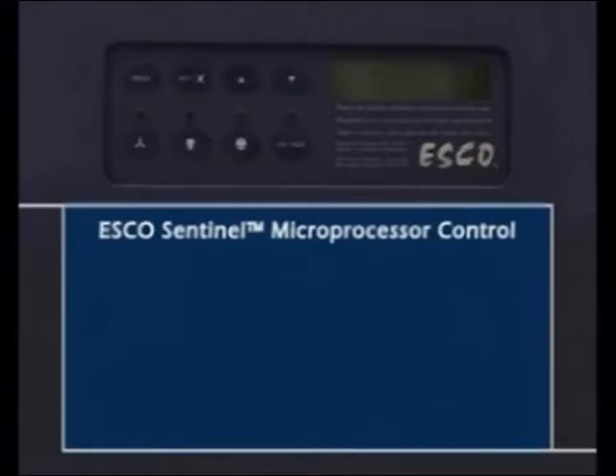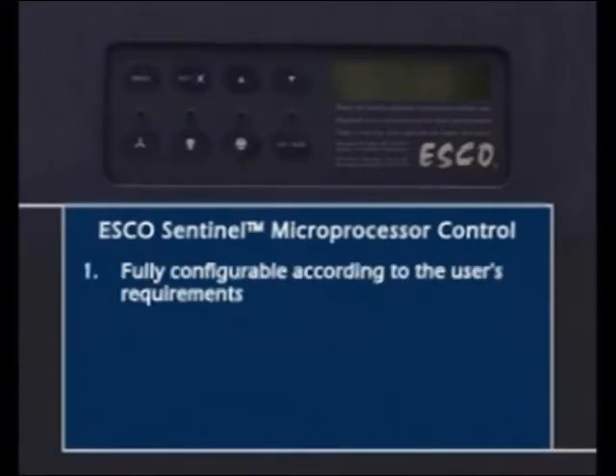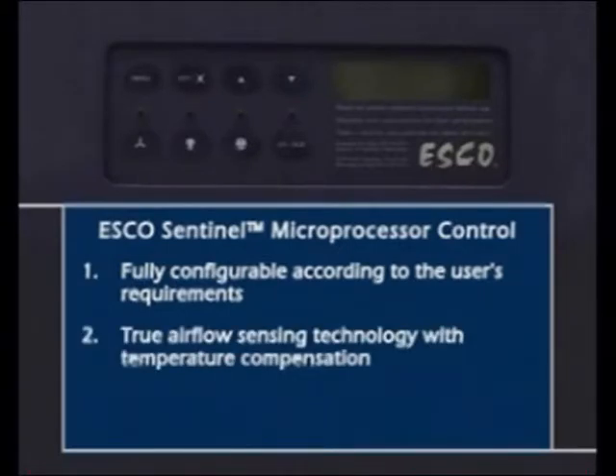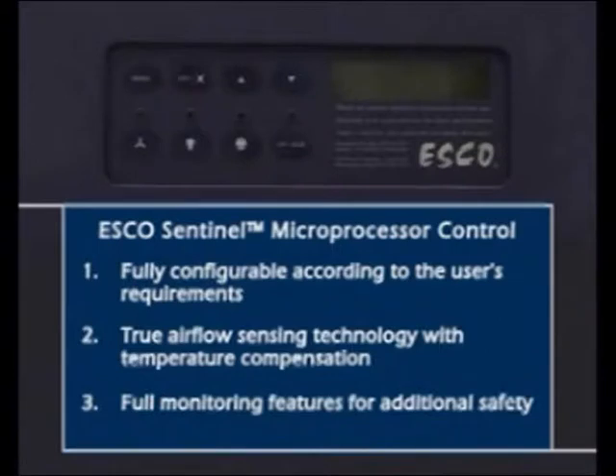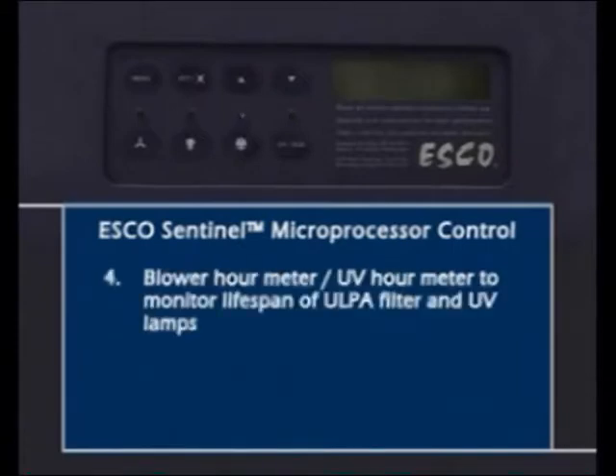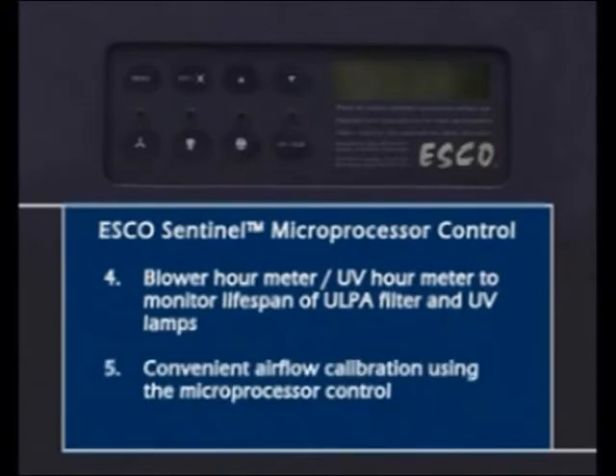Lab Culture Class II Type A2 biosafety cabinets are equipped with the Sentinel microprocessor control system. All control features and functions may be configured to suit the user's requirements. Cabinet airflow velocities are continuously displayed on the LCD screen. The Sentinel control provides intelligent hardware diagnostics and generates error message reports. The control system monitors blower usage hours to gauge ULPA filter lifespan and alerts the user when a replacement is required. Cabinet airflow velocity settings may be calibrated directly from the microprocessor control system.